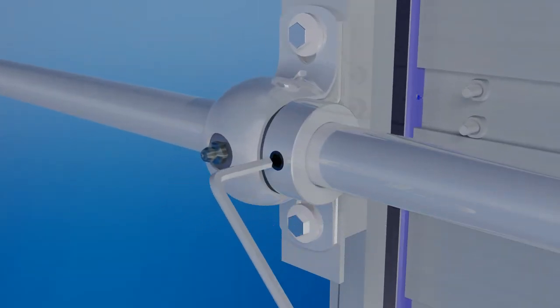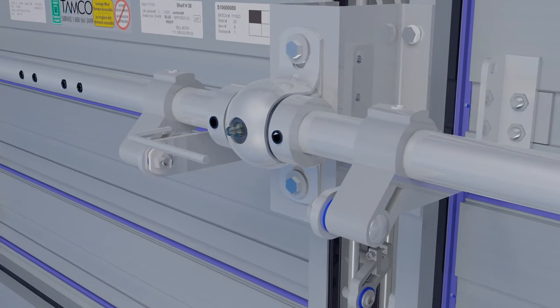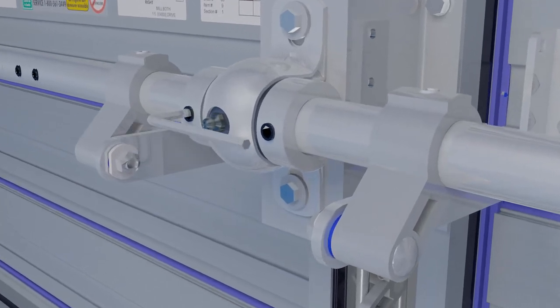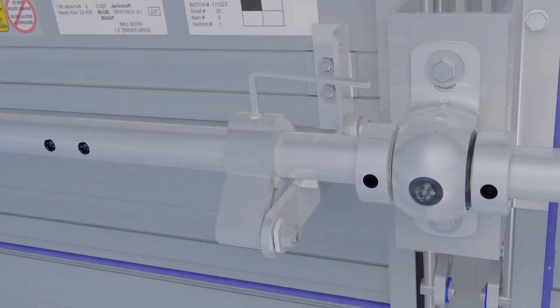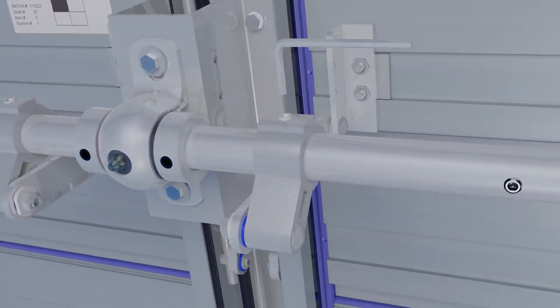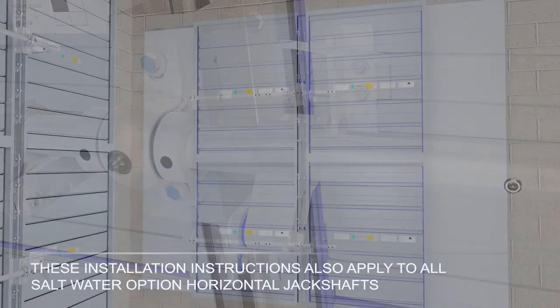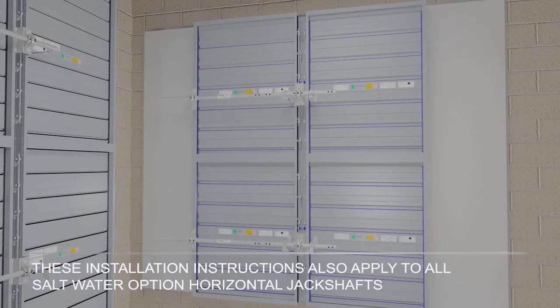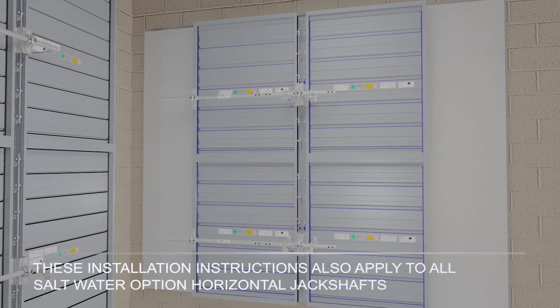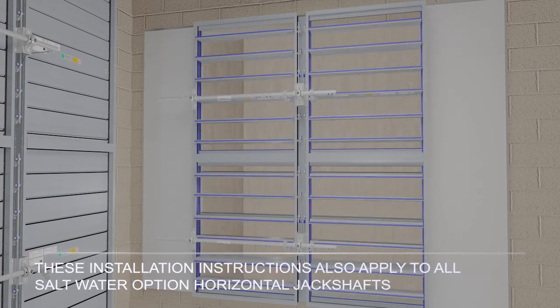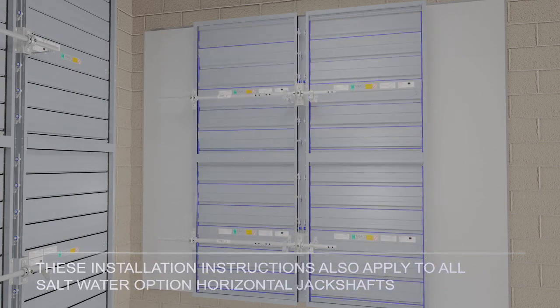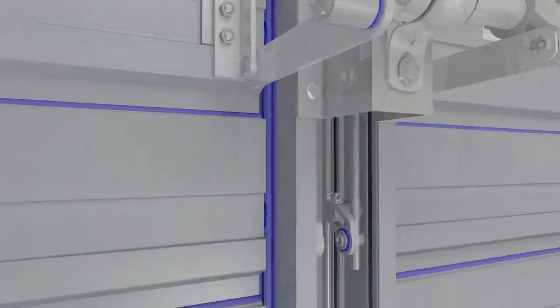Then tighten the set screws on all the locking collars and verify that all the remaining set screws are tight as well. The final step is to test the damper and jackshaft operation by manually rotating the 1-inch diameter shaft to ensure that both damper sections seal correctly.